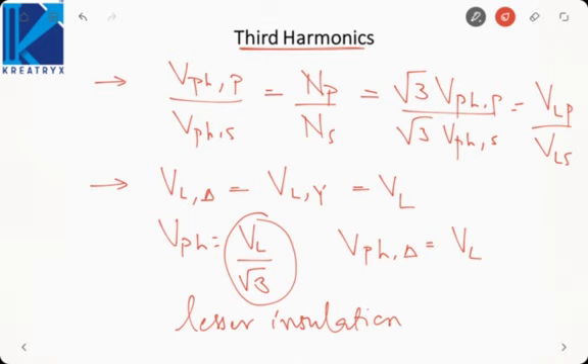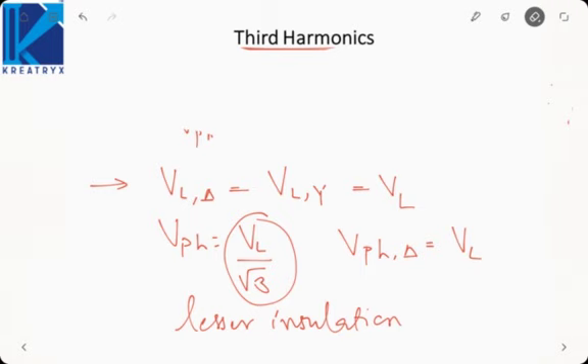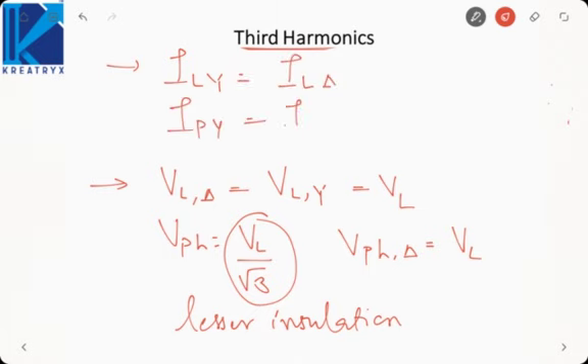Okay. But if we keep line current same, that is IL star is equal to IL delta, then IP star will be equal to IL and IP delta will be IL by root 3. So in case of star, phase current is more as compared to delta connection. That means the area of cross section of the conductor will be higher in star connection as compared to delta connection. Okay. So it requires lesser number of turns but thicker conductors. So thicker conductors will be employed in a star-star transformer as compared to delta-delta transformer.